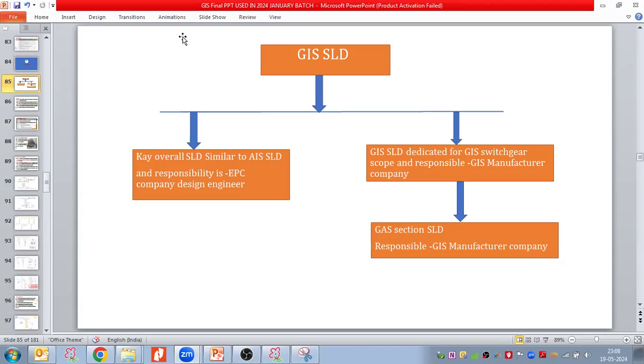In few cases, when the GIS supplier does the insulation coordination study in order to mitigate the VFTO, in those kinds of cases, they put the surge arrestor into the GIS, but which is only for mitigating the overvoltage, which is generated due to the transient operations of the switchgear. So for that, they provide additional surge arrestor into the GIS module. But if you are taking a project where you have the space, you can try to put the surge arrestor outside of the GIS. Santosh, I think in your project you have taken surge arrestor inside the GIS, right?